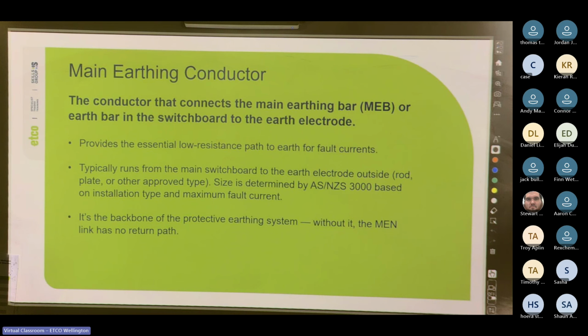So it's the most critical link in the chain. Think of the main earthing conductor as the motorway for fault current. Direct, low resistance, and always available. If this is missing or compromised, the MEN system doesn't work. So what happens in the event of a fault? We can have neutral return current flowing through the earth. Yeah, we're just having a review of the last topic, or at least parts of it. We're going to kind of breeze through it.